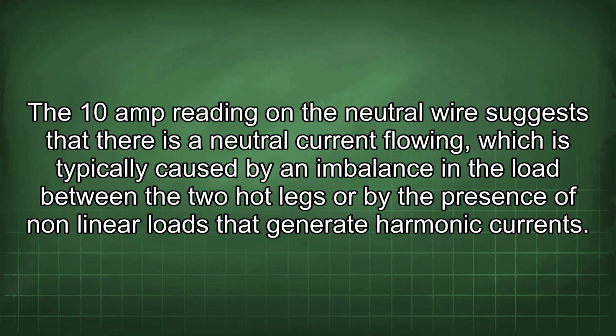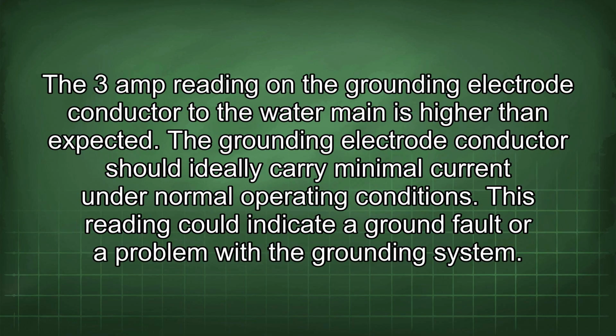The 10 amp reading on the neutral wire suggests that there is a neutral current flowing, which is typically caused by an imbalance in the load between the two hot legs or by the presence of nonlinear loads that generate harmonic currents. The 3 amp reading on the grounding electrode conductor to the water main is higher than expected. The grounding electrode conductor should ideally carry minimal current under normal operating conditions. This reading could indicate a ground fault or a problem with the grounding system.